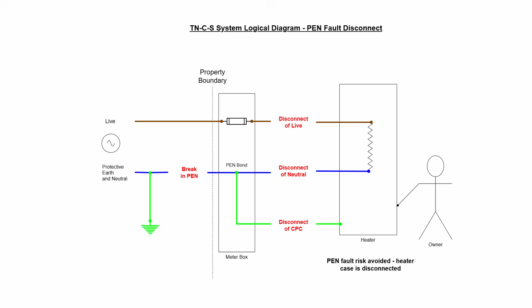This is how we know that my granny cable does not offer PEN protection, because there is nothing in it that breaks the CPC, which is a requirement for this sort of protection. At this point, I want to address another question from the comments, which was whether other protection mechanisms can save us from this fault. Firstly, RCDs, known as GFCIs in North America.